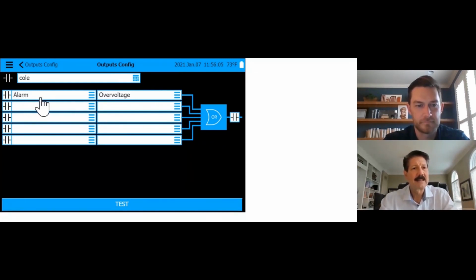So if we have a dedicated alarm, or maybe you need another motor run alarm, it doesn't matter, but you can isolate a specific one in the field if you need one. And so in this particular case, okay, it's an overvoltage, it's dedicated. If we run across an overvoltage condition, it will close this particular contact when it senses that. Now, what if I want to change that from an open to a close? Well, all I have to do is click on it. And now what will happen is with an overvoltage condition, the contact will open.